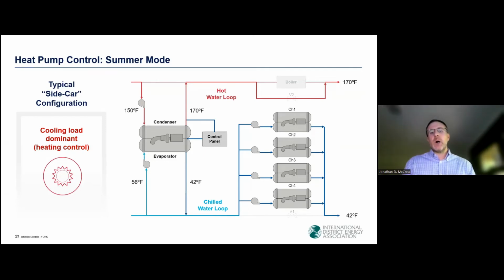We're using the heat pump's compressors to raise the heat to a useful temperature through the refrigeration cycle in order to produce the hot water. And we're simultaneously reducing the number of cooling tons that the downstream chillers have to produce. So that's where we get this double effect where we're getting beneficial heating and cooling, and we can achieve COPs that are 5.0 or higher. So obviously, depending on your gas and electric rates, this will vary, but you can really get some impressive operating cost savings as a result of this configuration.